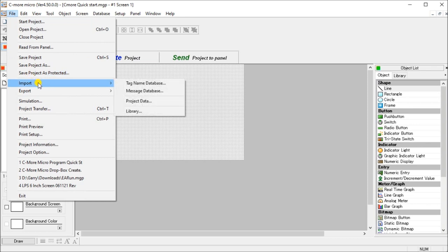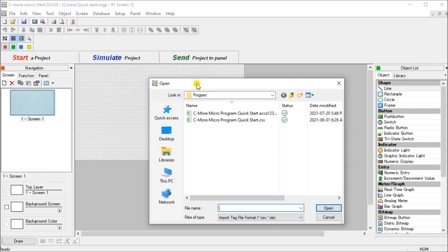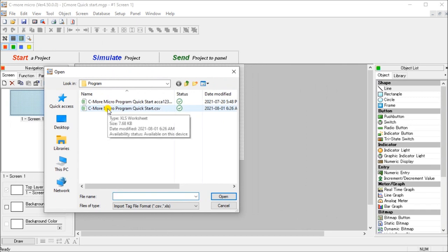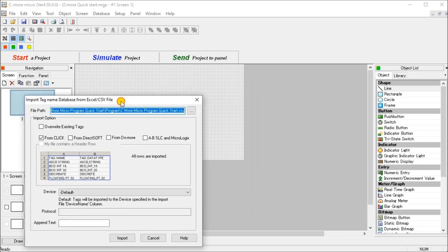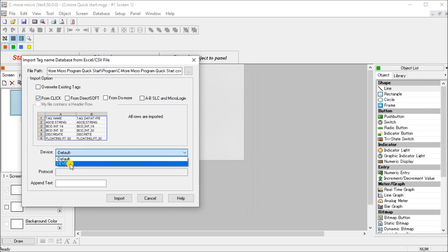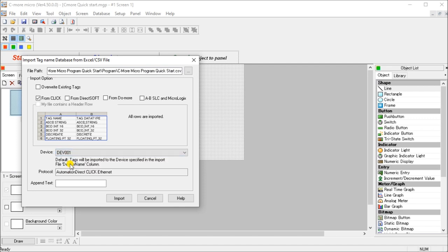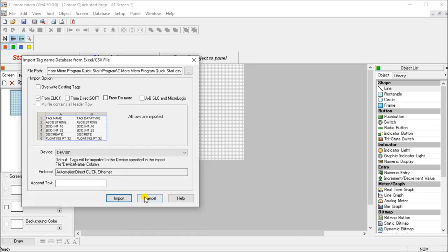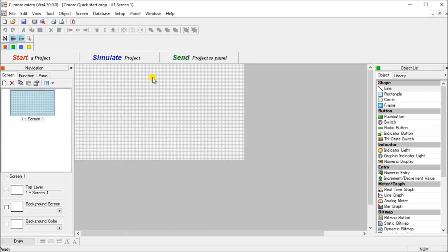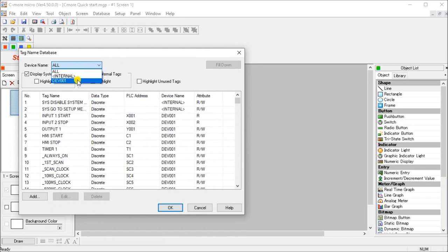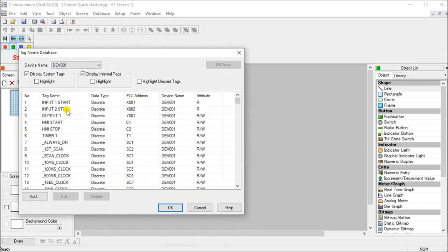Next what we'll do is take those tags that we exported from our PLC and we'll import it here. So file, import. And then we want a tag name database. And what we're going to do is select that same CSV file that we've saved before. It will actually ask us, it's coming from a click. And then it will ask us our driver. And we're going to go to DEV001, which is the device driver to that click that we just set up when we did the startup. We'll hit import. And there we go. So there are a couple of things that says unable to add, but it's already there. So let's hit cancel. And if we want to see those, we can hit database, tag name database. And here's all of my tags, or we can just look at the DEV ones and you can see my input start, stop, output. So that's already there that now I can use within my program.